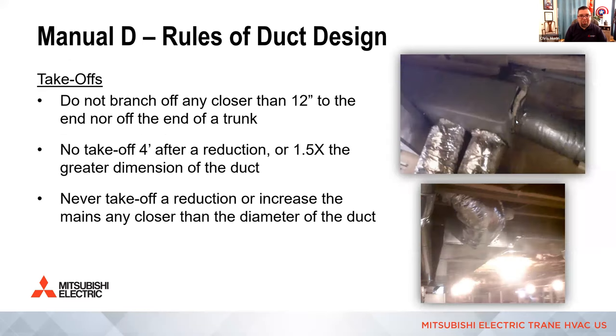Some more bad pictures. Don't branch off, this was the one that, please forgive me, I think it was Steve that brought up, any closer than 1 foot from the end of the trunk, that end cap. So you can see as an example what's bad. Somebody took something right off the end of the end cap on the top picture here. And that's obviously existing. And then they added two more really just to make sure there's nothing going to the entire system. So if you're within a foot of that end cap, it depressurizes the trunk and all the air goes to that one takeoff, or two takeoffs.